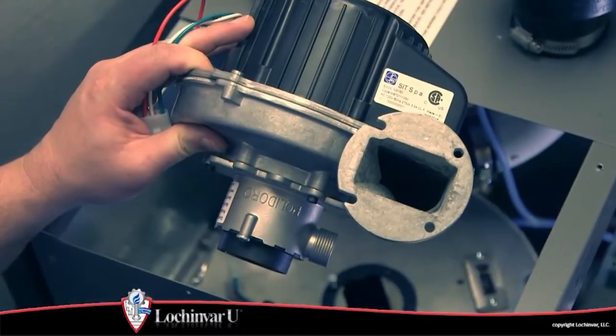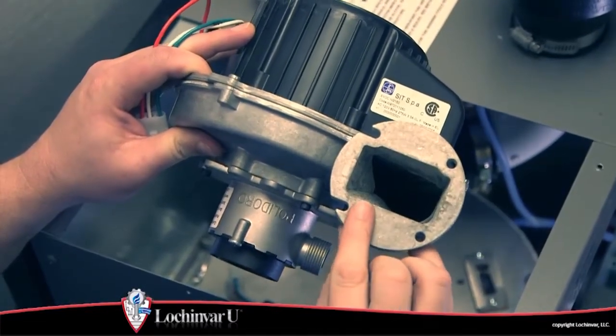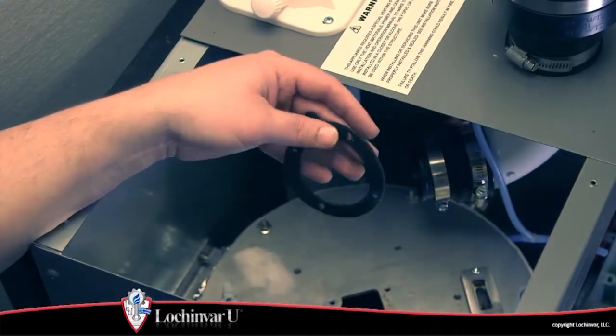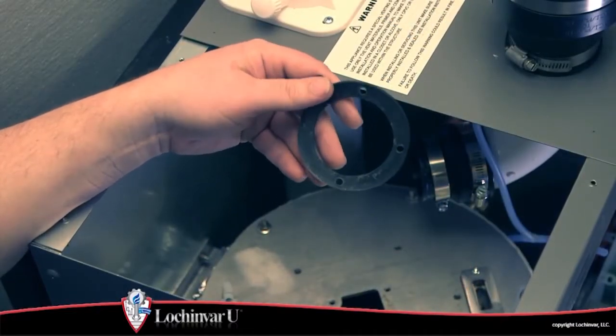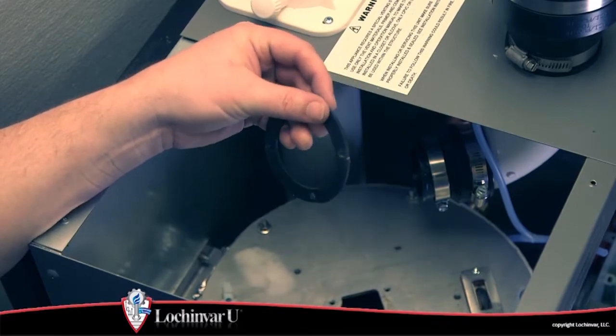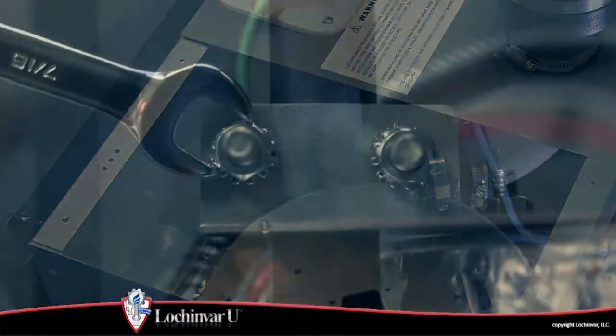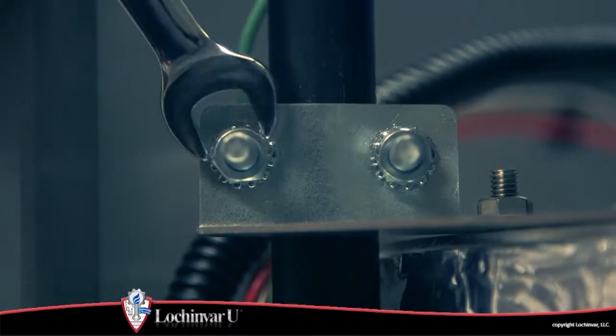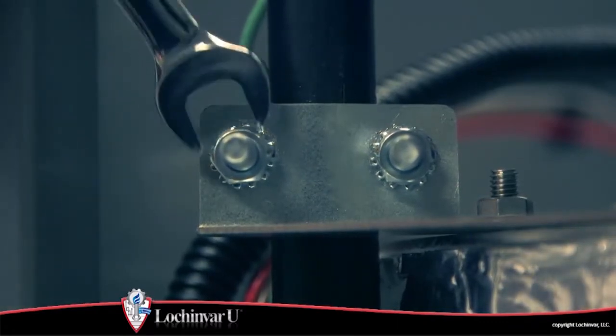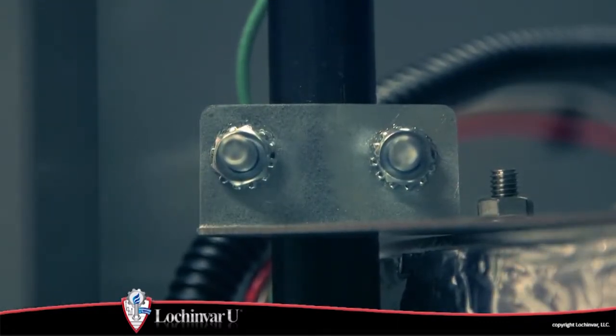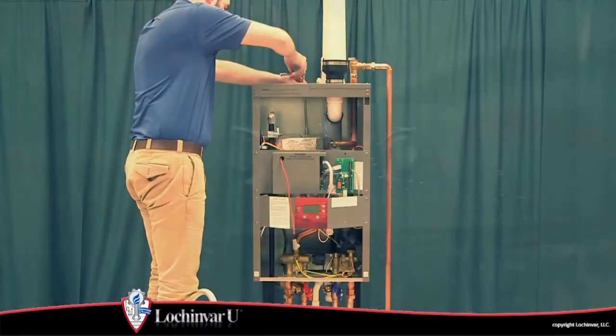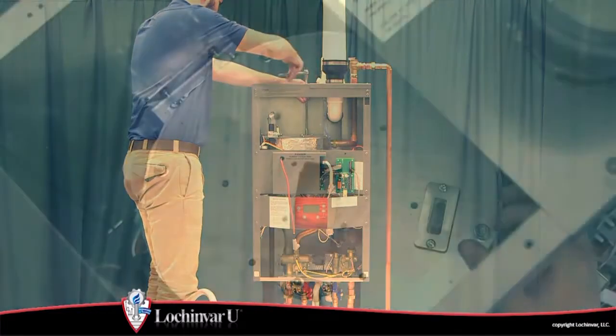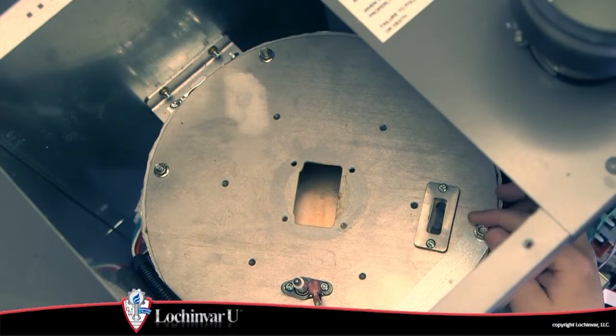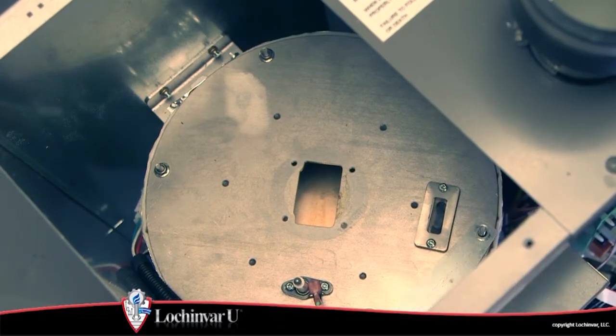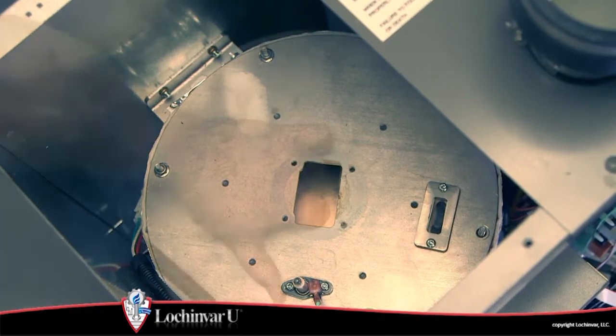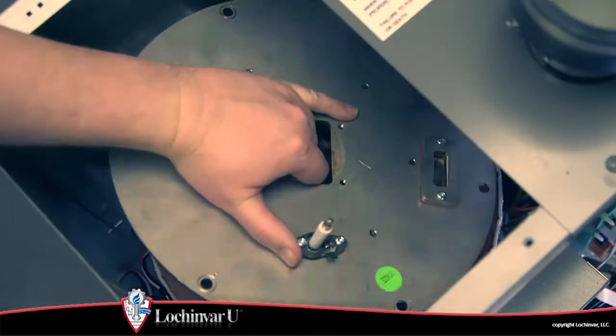A gasket is used to seal between the fan assembly and the heat exchanger top plate. Care must be taken not to tear or damage a gasket. If a gasket is damaged or torn, it must be replaced. Using a 7/16 inch wrench, loosen the 2 nuts securing the inlet gas pipe bracket to the inlet gas pipe. Then, using a 10mm wrench, remove the nuts that secure the heat exchanger top plate to the heat exchanger. Swing the inlet gas pipe bracket out of the way and remove the heat exchanger top plate.